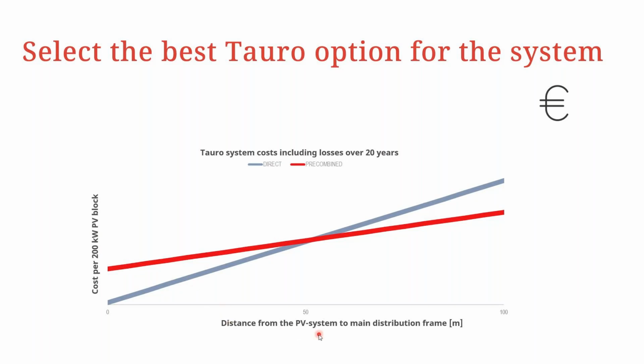The distance from the PV system to the main distribution frame is the crux of the matter. Depending on that distance and the cost of other components, at the beginning of the project, inclusive of CapEx and OpEx, the direct option is more economical, but as the length increases, it becomes more expensive. Conversely, the pre-combined version costs more at the CapEx stage, but as the distance between the PV system and the main distribution frame increases beyond a certain point, it becomes more economically viable than the direct version.